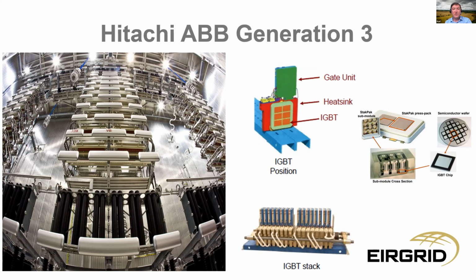When not in operation, all these areas within the valve hall need to be routinely inspected and maintained, where working at height is a risk. In the near 10 years of operation, Moore's law continues, and this generation of valve design has moved on. In today's world, multi-level VSC converters result in more efficiencies with lower losses, as an example.